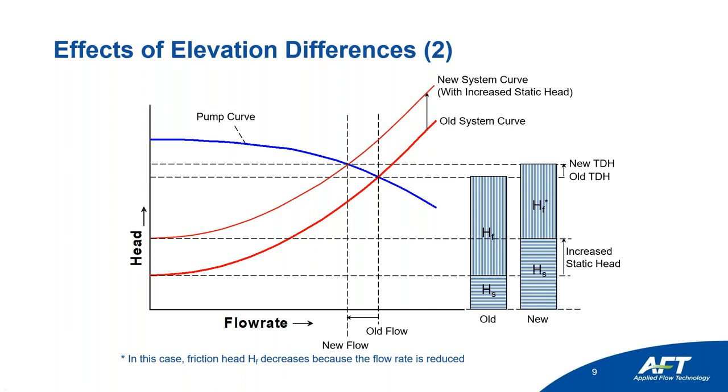Again, why do you care about this? Wherever these two curves are intersecting, that's really not the main thing that you care about. What's important is when you cross plot that efficiency curve, you want to make sure that whenever you have a change in your system, you pay attention to how your pump is operating in relation to the best efficiency point.